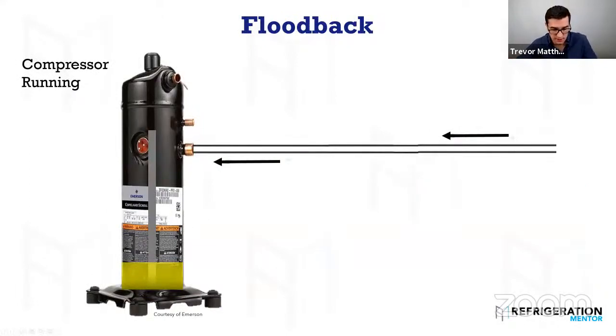Any questions? Let me just check because I know I'm going through a lot of stuff here because I only have so much time. I had a system where the evaporator superheat was 8 degrees F, but when I checked at the compressor, it was 55. Line set was very long, old, bad insulation. It was burnt. In this case, should I have flooded the evaporator? No, you need to fix the line set. Was the suction line sized properly? Because if you don't have the proper velocity going through the suction line, you're not going to be moving the gas properly to cool the compressor. If it was a refrigerant-cooled compressor, you need that gas to cool the motor. And either the line set was bad, or that suction line with bad insulation was running through a heated space, picking up all that heat. So you needed to replace all that insulation. So hopefully that helped.